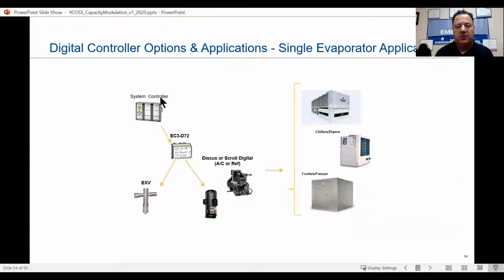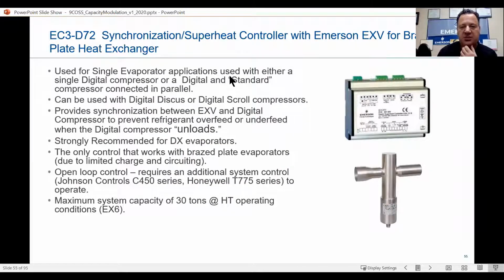You can see the system controller over here. We have that EC3-D72 board, EXV, our compressor. Could be a Discus or a scroll digital AC refrigerant over here, and all these different applications. All right, this controller, we're going to ask you to use this controller when you're using an EXV. If you're using it for a single evaporator application, use with either a single digital compressor or a digital and standard compressor connected in parallel. Can be used with digital Discus or digital scrolls, and it provides synchronization between the EXV and the digital compressor to prevent refrigerant from overfeeding or underfeeding when the digital compressor unloads. That's the huge part of it.